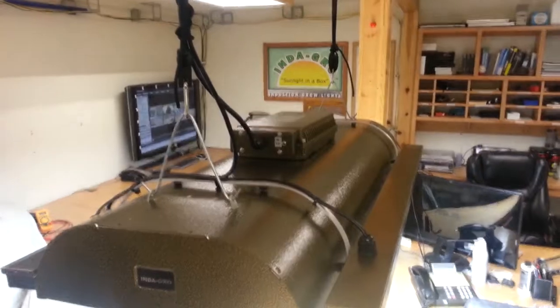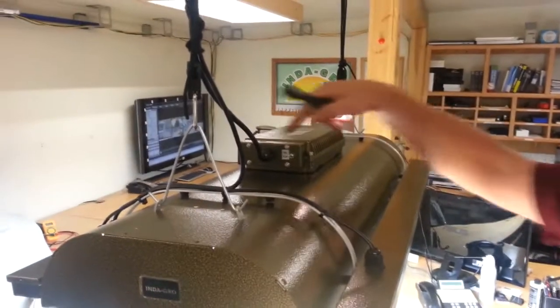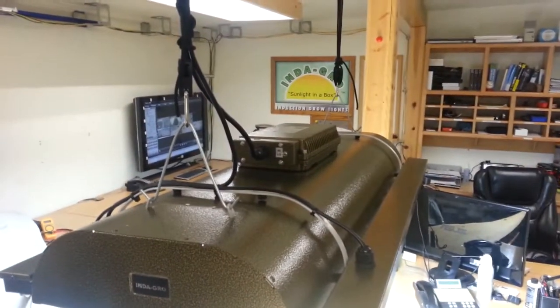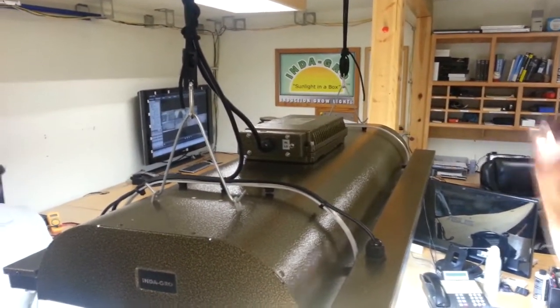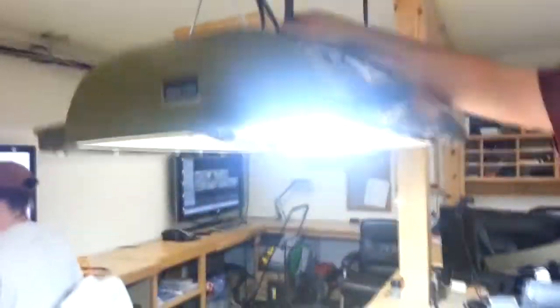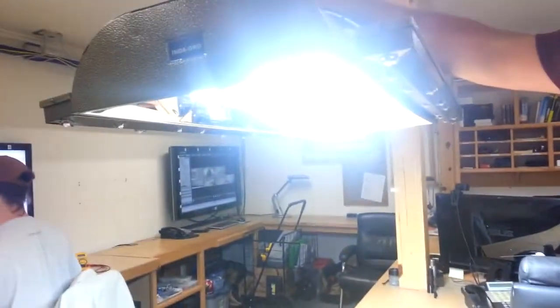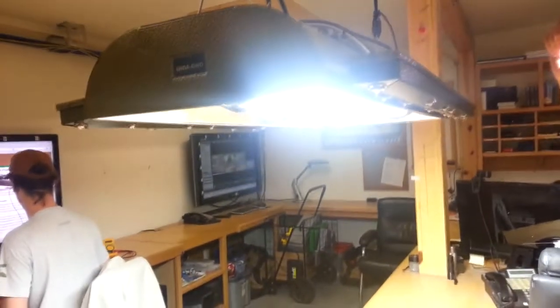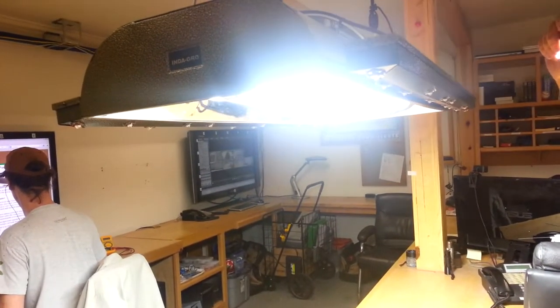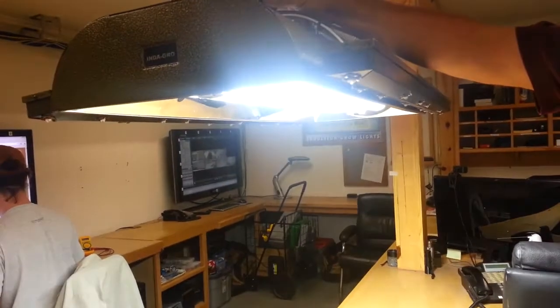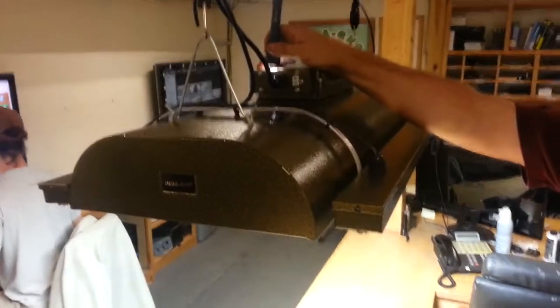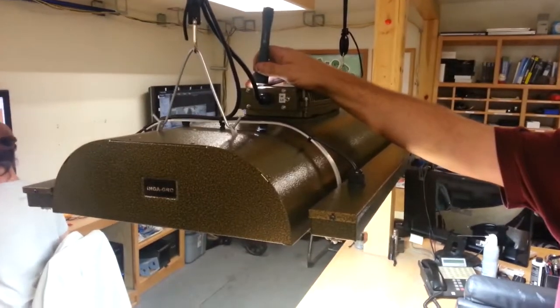All right. On top of the greenhouse lights, this is called our daylight harvester series. It has a sensor and that sensor is designed, especially a very large greenhouse where light levels will vary. It's designed to lower the light levels to account for available sunlight down here. So if I have a situation where I have maybe only 50% of the light level needed, then it's going to react accordingly. The plants are still going to see full light levels because it's going to be a combination of sun and artificial light.